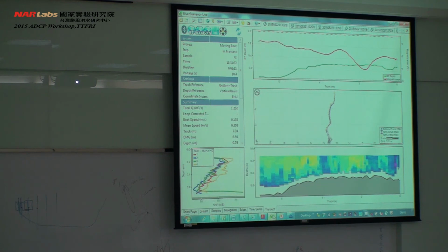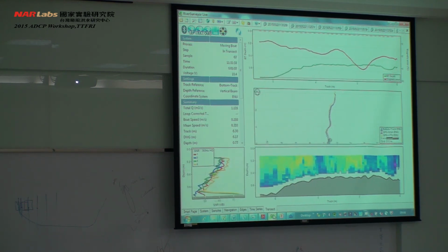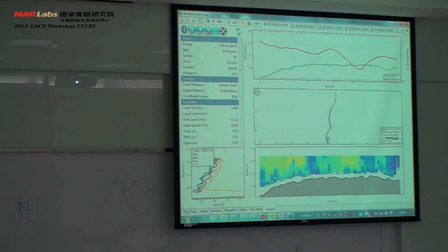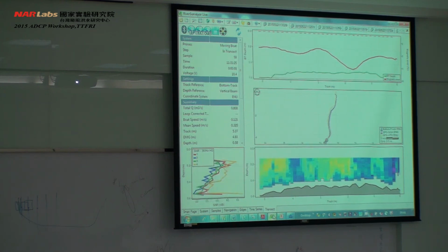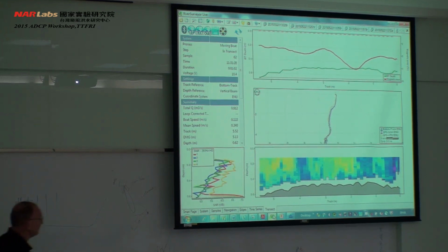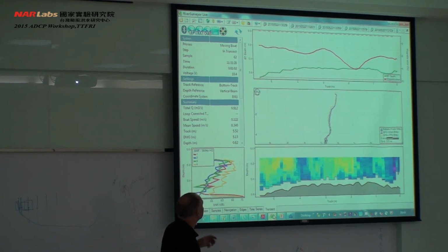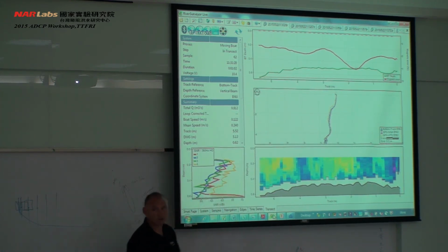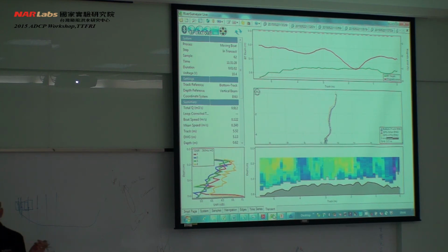If we look at the data from here, it was definitely more obvious in the stationary software, but you see that beam 4 is slightly stronger in signal than the other ones. It's just a function of the ceramic that's being used. It's a more efficient ceramic than the other three. They have a quality criteria with the SNR as to what they will allow, the difference between the four ceramics, and it's passed that test.